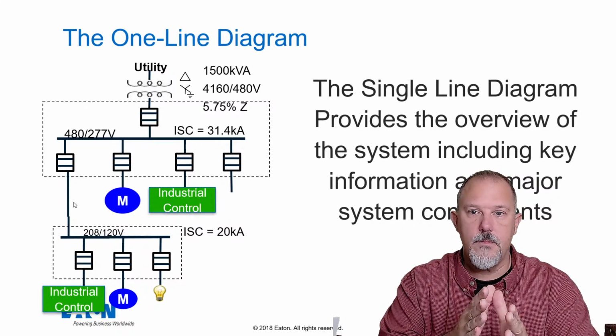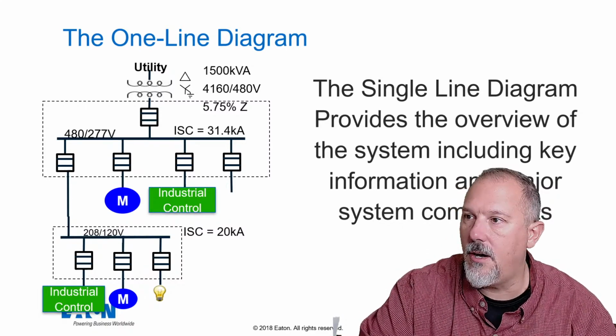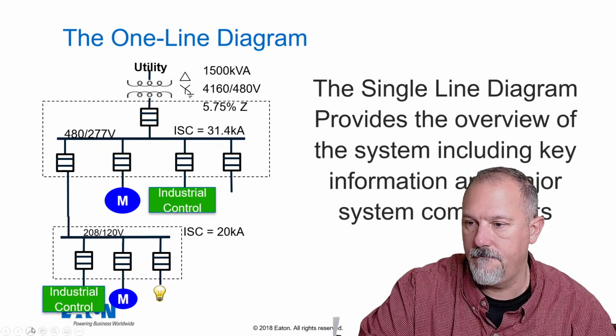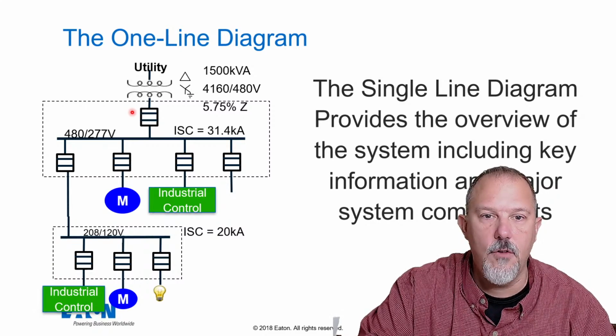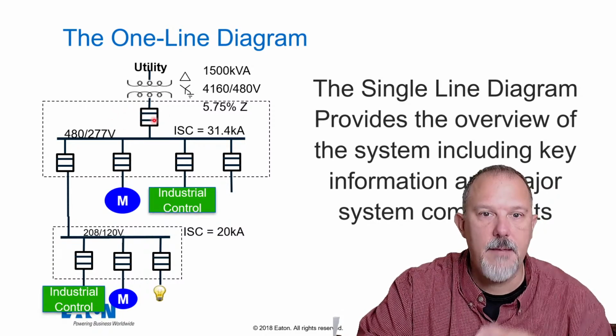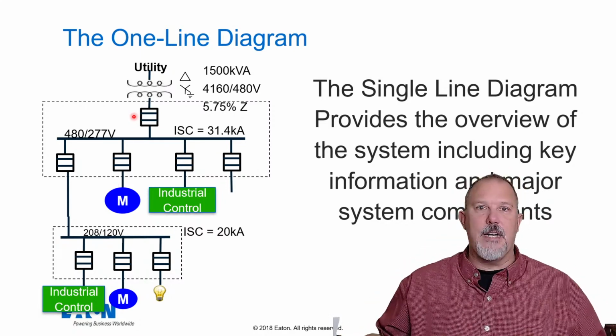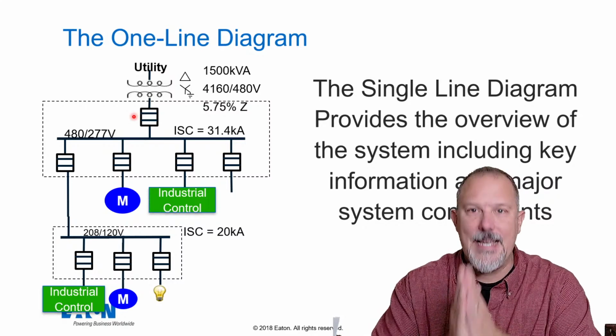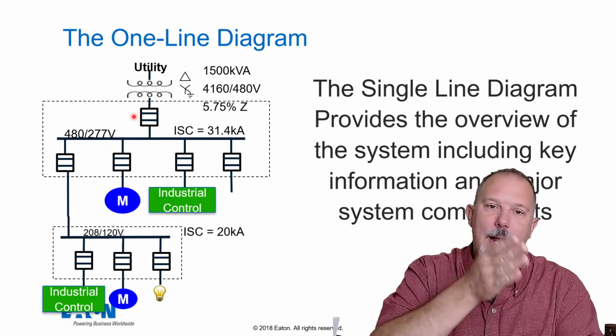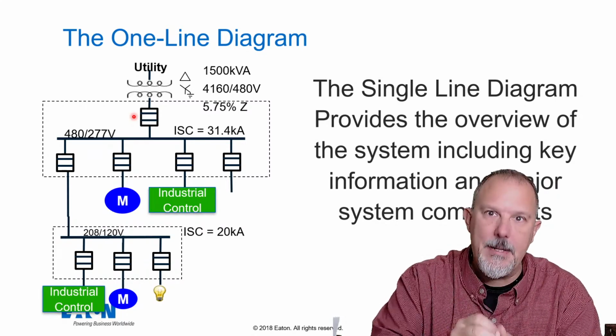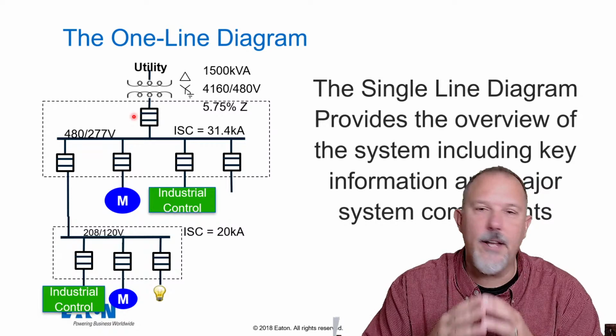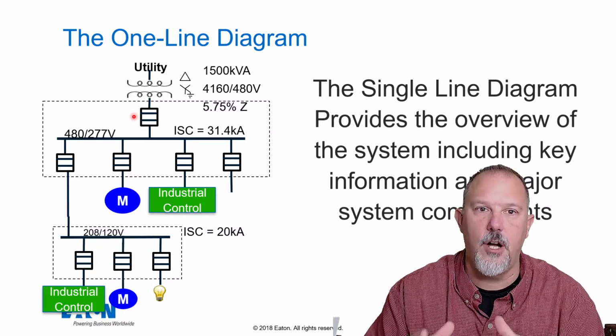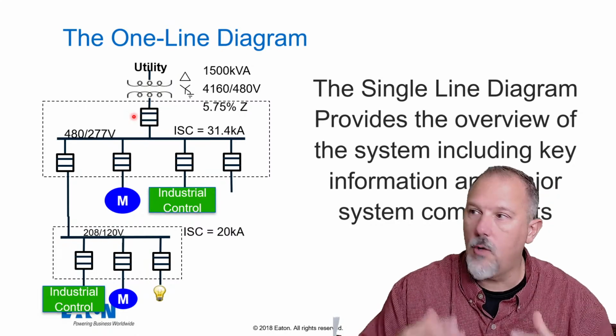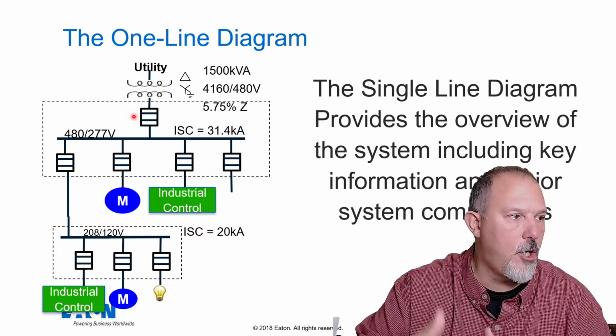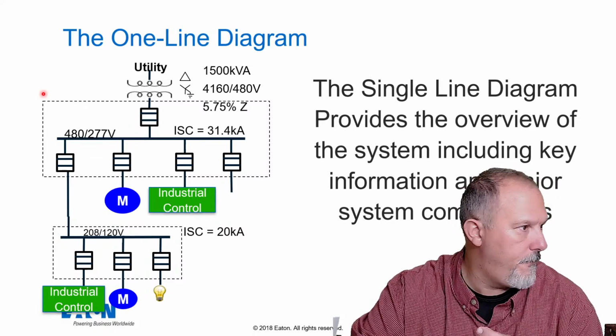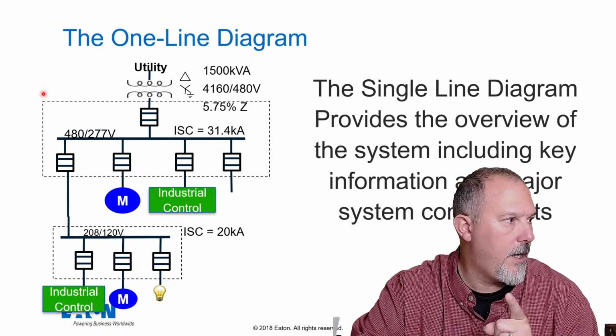Now, I've had people say that because they have this overcurrent protective device right up here, it limits the current to everything downstream. But that's not the case. And the reason is, when I talk about current limiting devices, I am not current limiting over the entire range of the fuse or circuit breaker. What do we mean? At what point does a fuse go into the current limiting region? I've got to look at a fuse curve, and I've got to find one now.